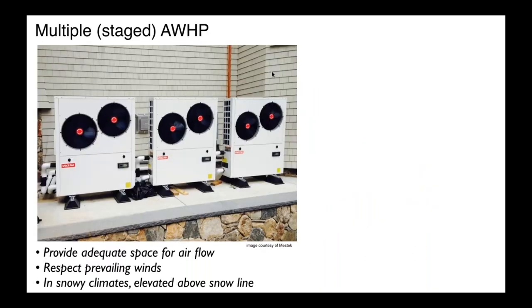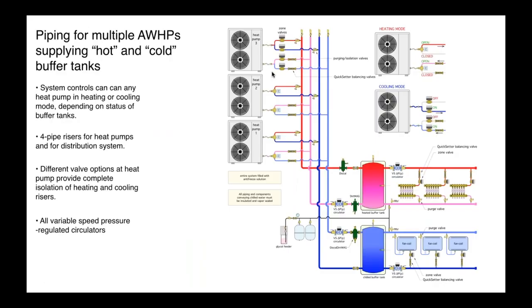Real quick, you can do multiple air-to-water heat pumps. Okay, we've got a pipe schematic in Hydronic on this. Basically, it's a four-pipe riser system. Each of these heat pumps can be independently controlled, turn on and heating, turn on and cooling. And essentially, whatever the output of the heat pump is, it's directed into either the hot buffer tank or the chilled water buffer tank. And from there, we go out to suitable chilled water terminal units, or I'm just showing some radiant panels here.